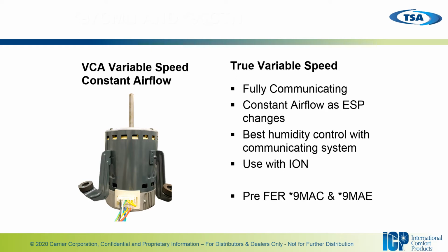All right, the variable speed constant airflow motor. This is what we consider in the industry a true variable speed motor. It is a fully communicating motor, which means it communicates directly with the board to and from. It receives signals from the board, and the motor also sends signals back to the board. On this motor, you're typically going to see an extra wire on the control side. That extra wire is the feedback returning to the board. This allows the motor to communicate the RPM back to the control board and allows the control board to make adjustments against the RPM speed.